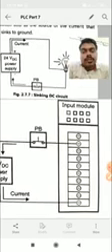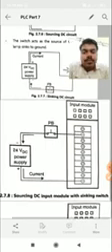Then replace this lamp with the input module. Same circuit is there, just replace the lamp with the input module in the first diagram, with the 24 volt supply. So what will be in this case? Sourcing DC input module with sinking switch. Let's say this is a switch. Let's see the current direction. The plus is given here and minus is there, so the current is traveling from plus. Firstly the input module acts as a source and the sink will be the push button, meaning this input module is providing current to the push button.